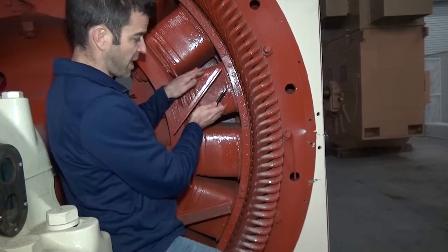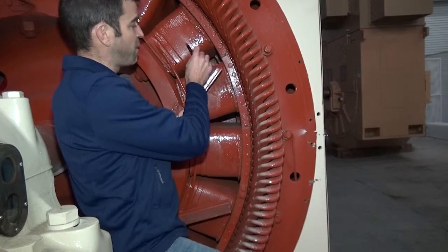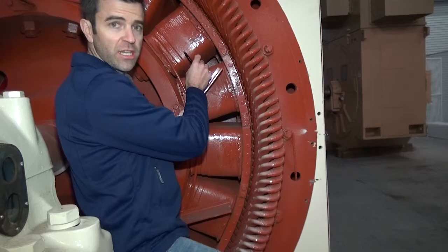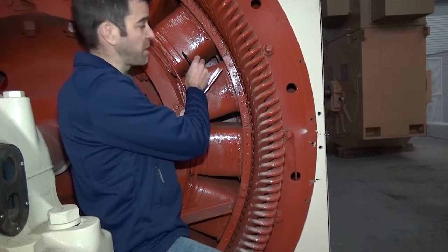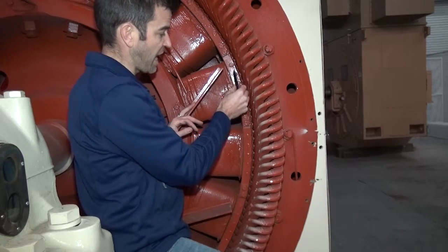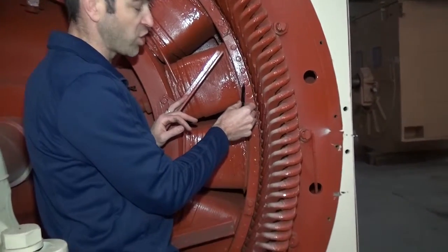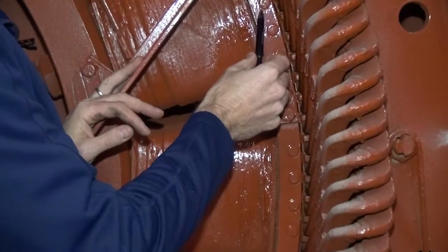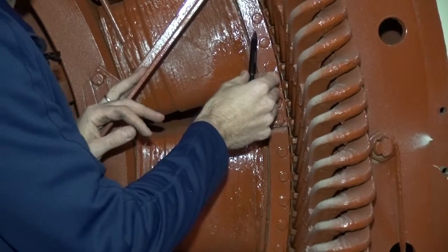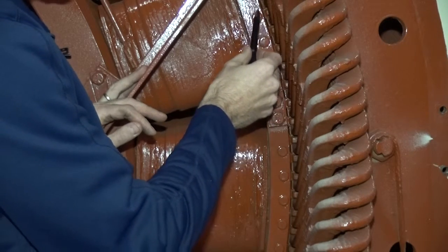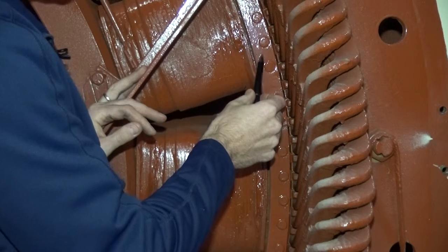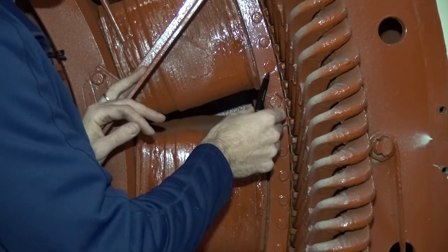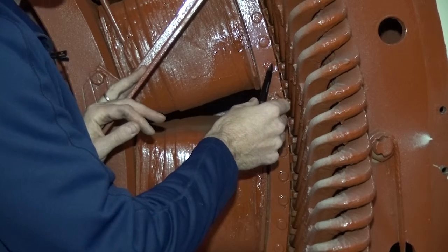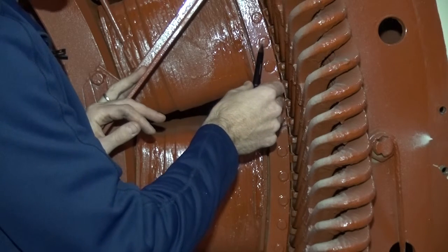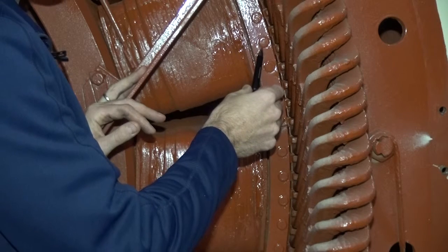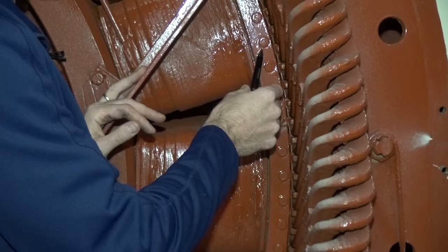Here we have one pole and another pole and another pole. And remember, the pole is what's used to synchronize the machine. This is what's operating while the motor is at synchronous speed. But around the pole, we have cage bars, and these are brazed into an end ring. Now, these brazed joints are susceptible to chemical attack or aging, so we want to have a very careful inspection of this area. You can see that this machine is nice and shiny red, and there's no evidence of oxidation. But if you see green powder or other evidence of rust or oxidation, we definitely want to take photos of that and add them to the report, because a repair may be required in the near future.